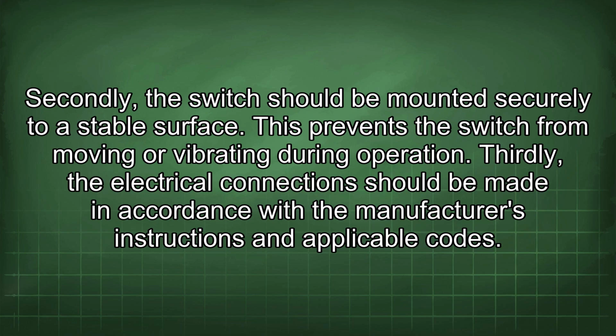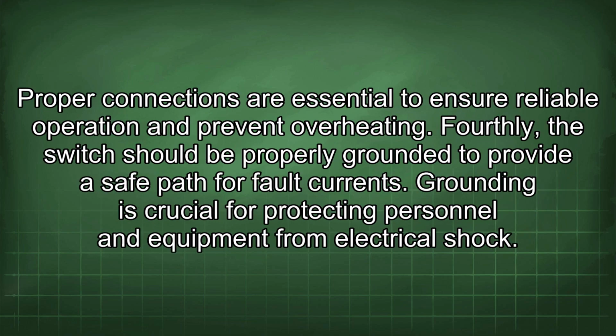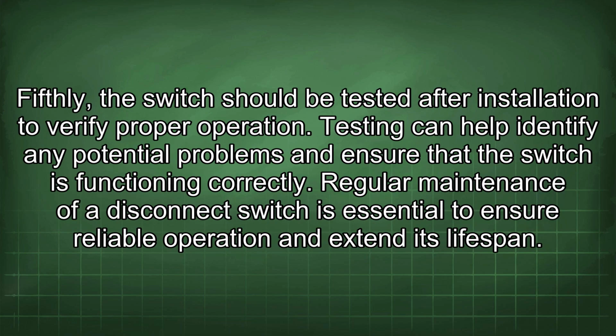Secondly, the switch should be mounted securely to a stable surface. This prevents the switch from moving or vibrating during operation. Thirdly, the electrical connections should be made in accordance with the manufacturer's instructions and applicable codes. Proper connections are essential to ensure reliable operation and prevent overheating. Fourthly, the switch should be properly grounded to provide a safe path for fault currents. Grounding is crucial for protecting personnel and equipment from electrical shock. Fifthly, the switch should be tested after installation to verify proper operation. Testing can help identify any potential problems and ensure that the switch is functioning correctly.